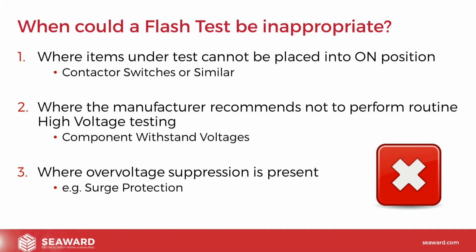Now, if you consider something like a desk lamp, and if we were performing the test on a lamp, let's say the switch is halfway up the cable, the switch is in the off position. We've got no guarantee that we're testing beyond that switch. We may only be testing that short space of cable from the plug up to the switch. So we need to make sure the switch is in the on position in order to test the product fully.